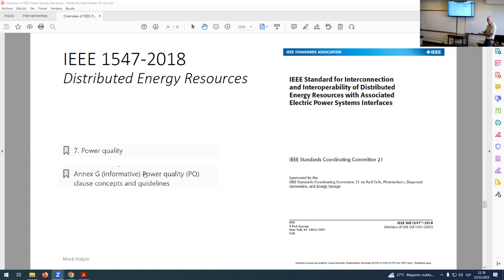And these are documents that describe the requirements for interconnecting generation equipment to a utility company. There's all kinds of things to worry about: ride through, voltage support, reactive power support, grounding, ramp rates, all that kind of stuff. And all of those things are considered in 1547. But we're only talking about power quality. There's one chapter in 1547 that talks about power quality, and then there's an annex in the back that gives a little bit more information. So just thinking about those two.